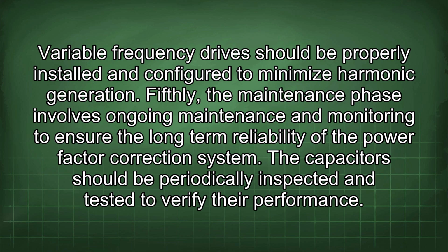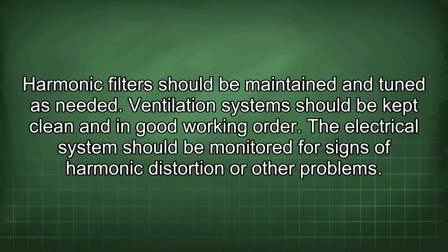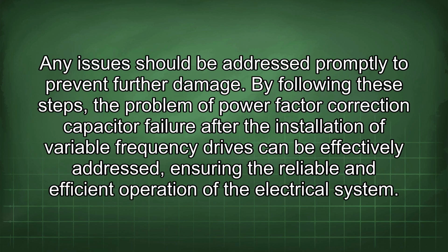Fifthly, the maintenance phase involves ongoing maintenance and monitoring to ensure the long-term reliability of the power factor correction system. The capacitors should be periodically inspected and tested to verify their performance. Harmonic filters should be maintained and tuned as needed. Ventilation systems should be kept clean and in good working order. The electrical system should be monitored for signs of harmonic distortion or other problems. Any issues should be addressed promptly to prevent further damage.